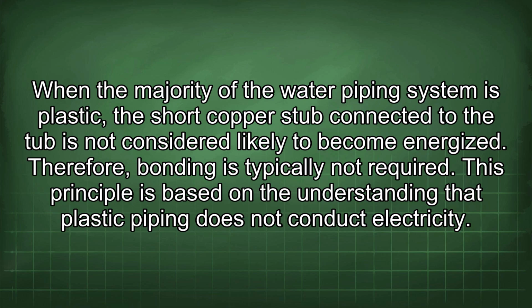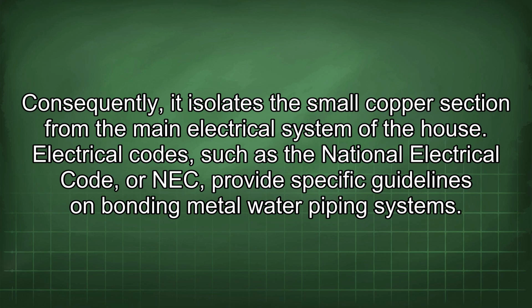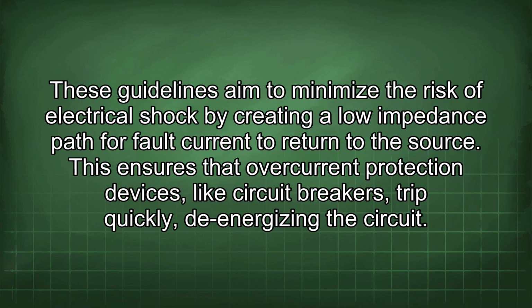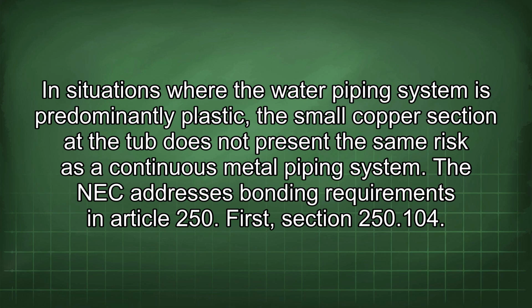This principle is based on the understanding that plastic piping does not conduct electricity. Consequently, it isolates the small copper section from the main electrical system of the house. Electrical codes, such as the National Electrical Code, or NEC, provide specific guidelines on bonding metal water piping systems. These guidelines aim to minimize the risk of electrical shock by creating a low impedance path for fault current to return to the source. This ensures that overcurrent protection devices, like circuit breakers, trip quickly, de-energizing the circuit. In situations where the water piping system is predominantly plastic, the small copper section at the tub does not present the same risk as a continuous metal piping system.